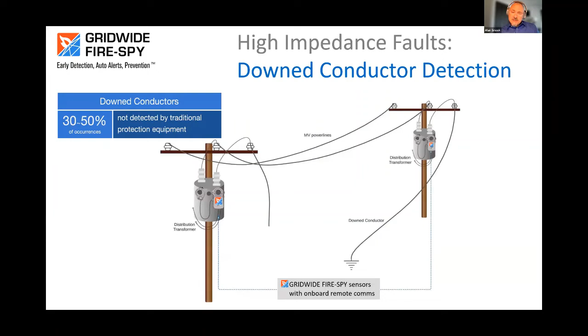What you're looking at is an incident that occurred in June of 2020. As Murphy's Law works, between 3 and 3:15 a.m., you can see where my pointer is, all of a sudden voltage dropped out substantially in the circuit feeder that we had coincidentally just been monitoring with multiple advanced transformer infrastructure devices. What happened is a primary side conductor that was on a pole contiguous to us.